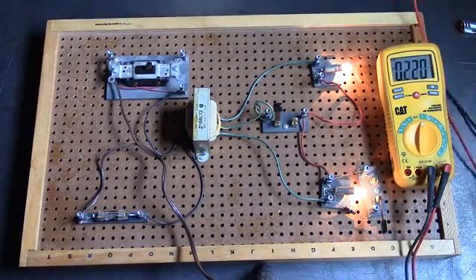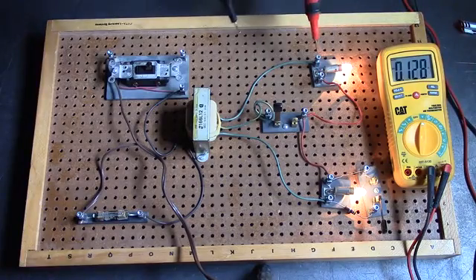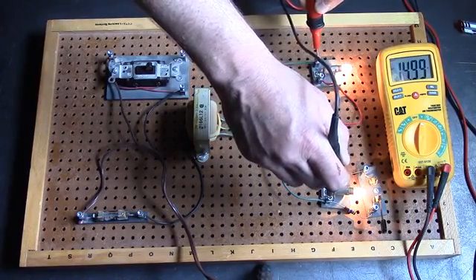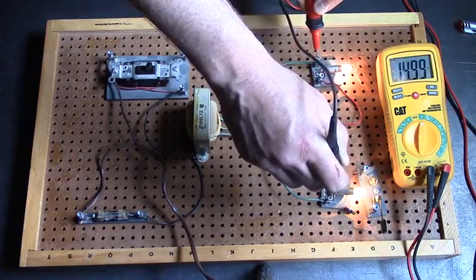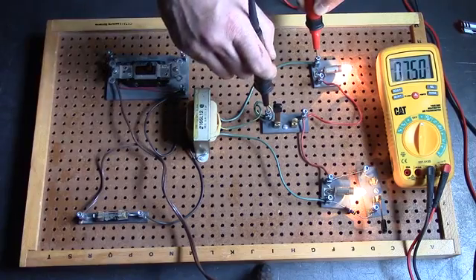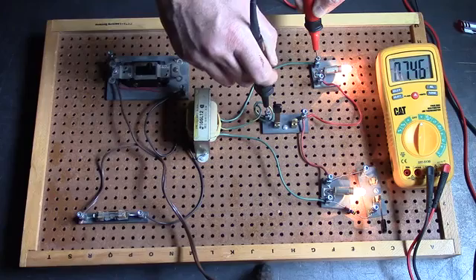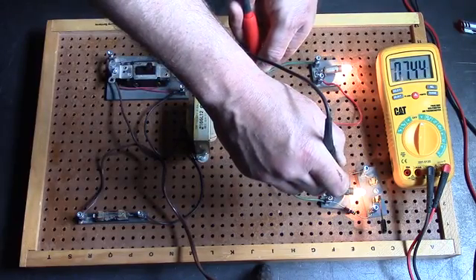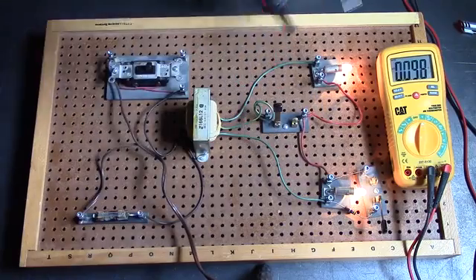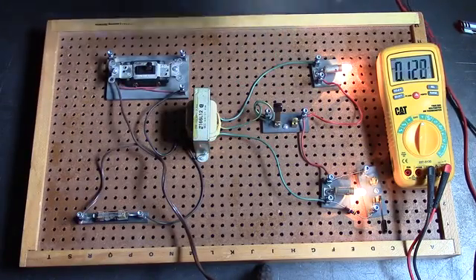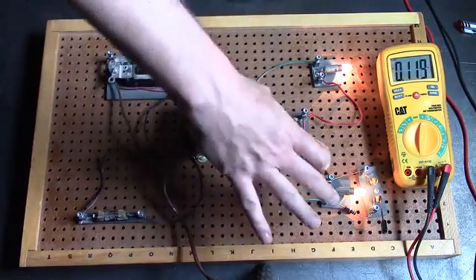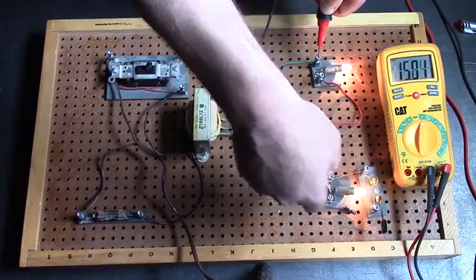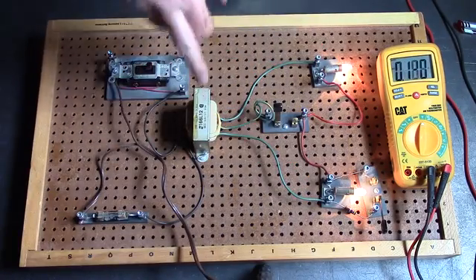So I've got my voltmeter on AC volts auto ranging and I've got from the outside two legs it's reading 15.14, 14.99 volts, 15 volts dead on. If I go to the neutral from this side 7.46 volts, 7.45. If I go from this side to the neutral 7.45 again. So those aren't adding up completely, I've obviously got a little bit of a voltage drop through the wires but approximately half voltage on this side of the neutral tap, approximately half voltage on this side of the neutral tap and again back to full source voltage from the outside two legs. So that's how a neutral is created on the secondary side of a transformer.